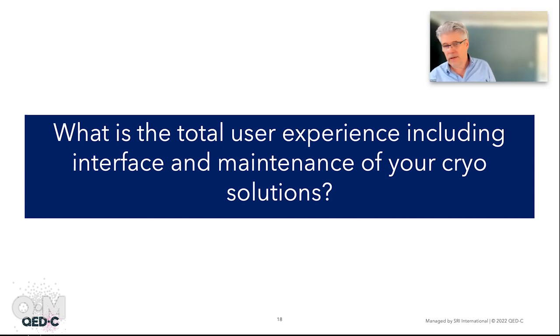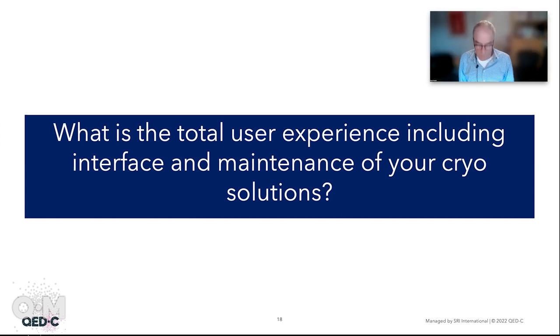Great, thank you. So Stuart. Thank you, Mark. From our standpoint at NanoScience, I would say the focus really comes down to two areas, one of which is remote access. Our Proteox OS, which has its roots in the Triton system, expanded on remote accessibility. A lot of our customers were able to access their systems during COVID remotely, very easily, very quickly. And with the new Proteox platform and the OS behind that, we've been able to expand that. So a lot of the functions now are completely accessible remotely, as long as the user has access to their local internet.